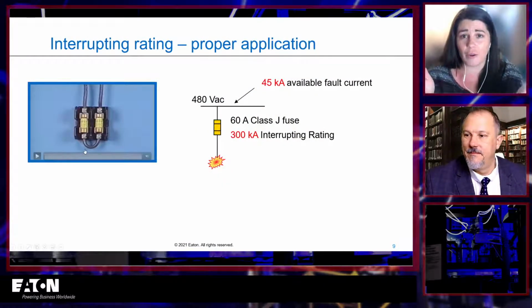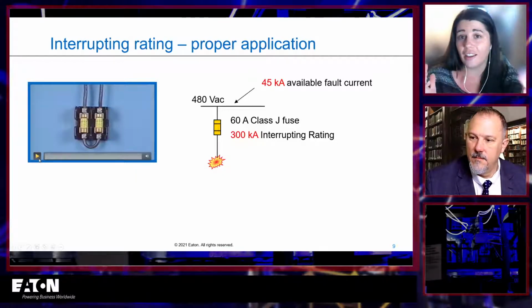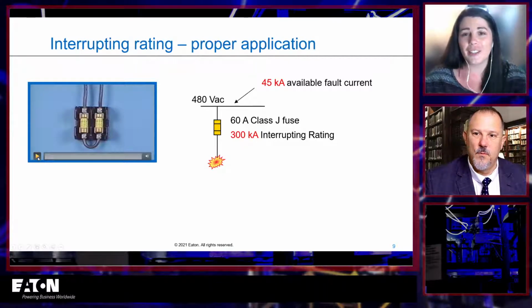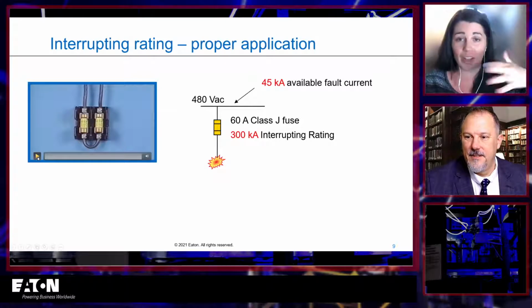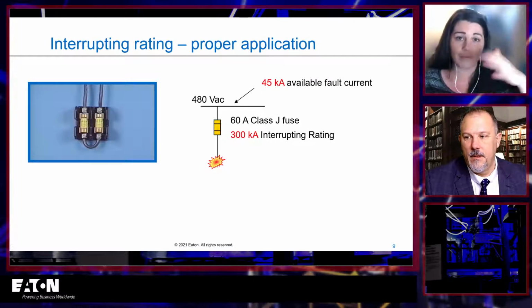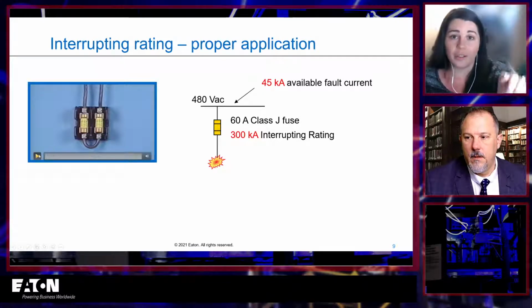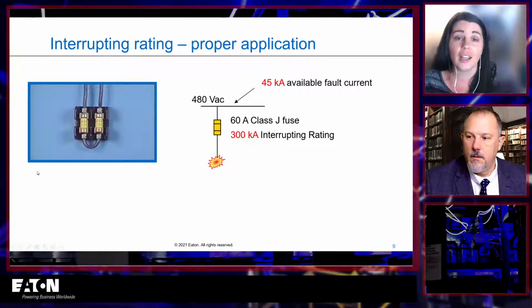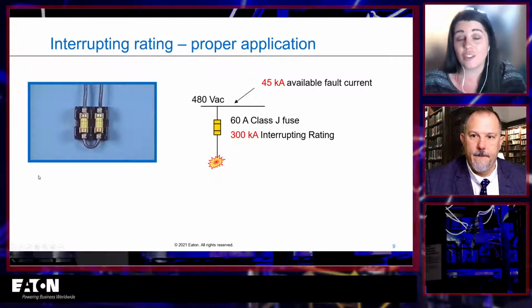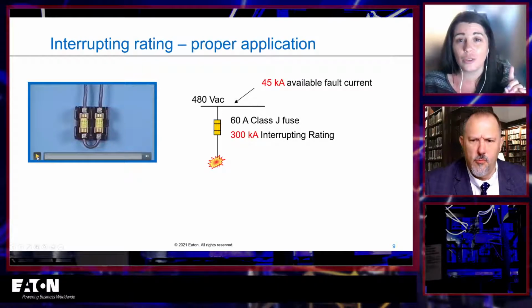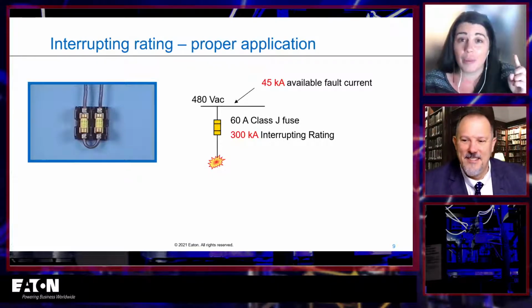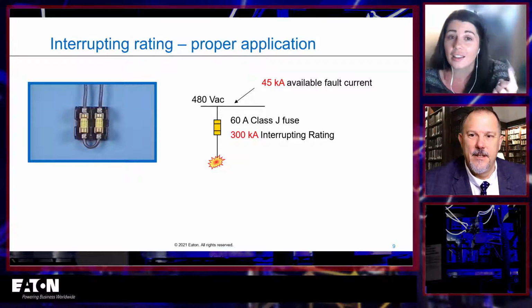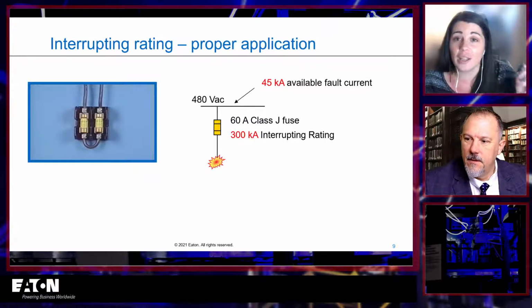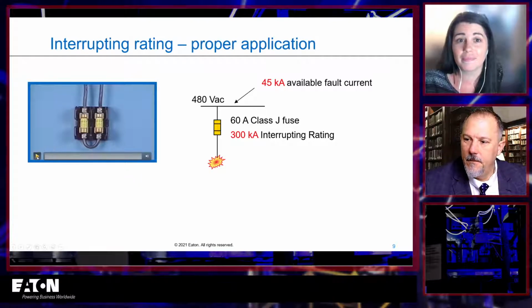So then of course, the most boring video you can ever watch is the proper application of a current-limiting fuse. So we have the exact same fault, again, exact same setup, voltage, available fault current. We've shorted it across the line side, but now we have a 60 amp class J fuse that has a 300,000 amp interrupting rating. And what you'll hear, there's a beep. When the beep occurs, that's the fault. So you can play it. There we go.